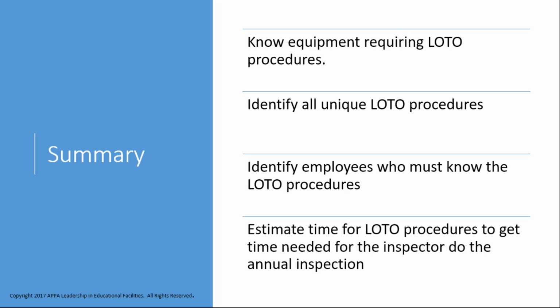Finally, estimate the time for each lockout tagout procedure. The sum of the times for the list becomes the total time needed for the inspector to observe the minimum number of procedures annually to ensure compliance. At the time of the annual inspection, add the time for the annual inspection to the PM schedule. That way you're able to plan your preventive maintenance and the time needed for the inspection and include enough time for the documentation.